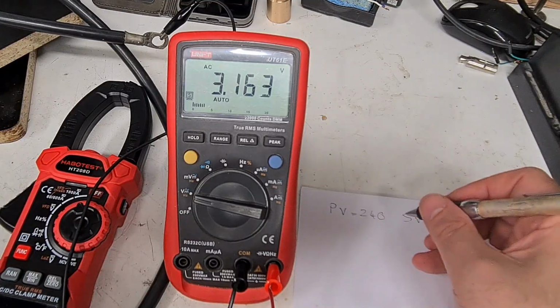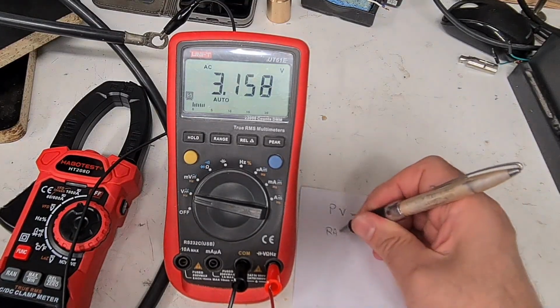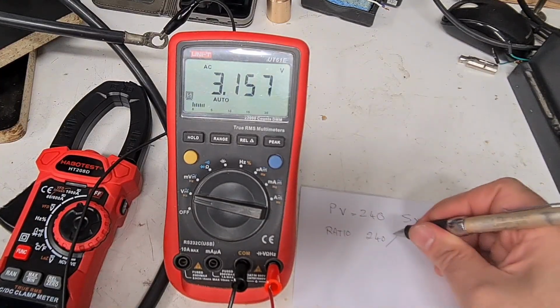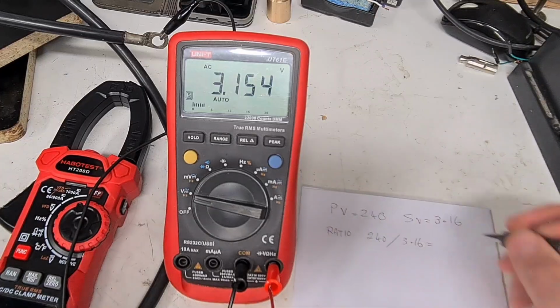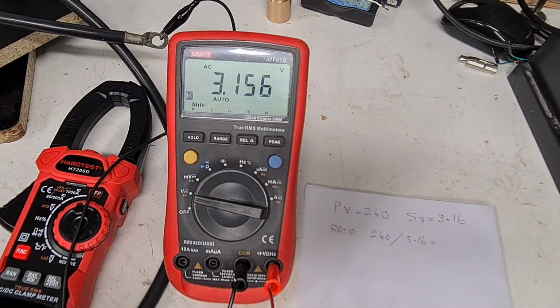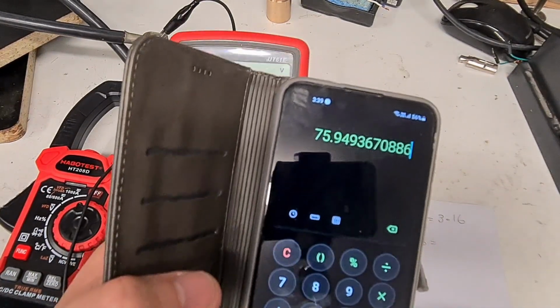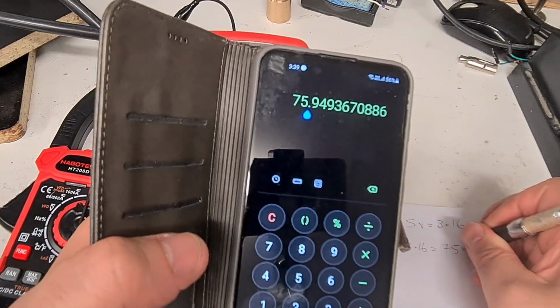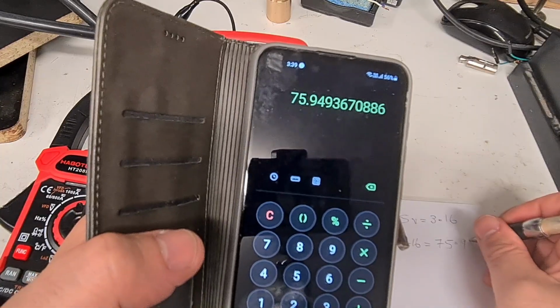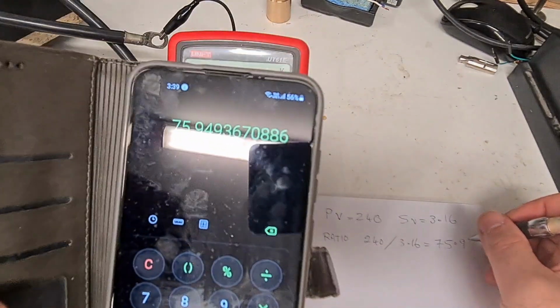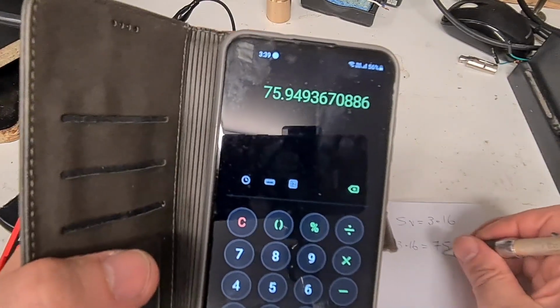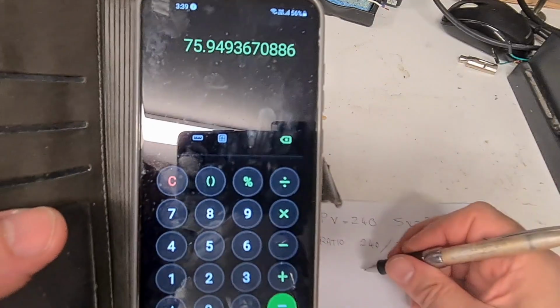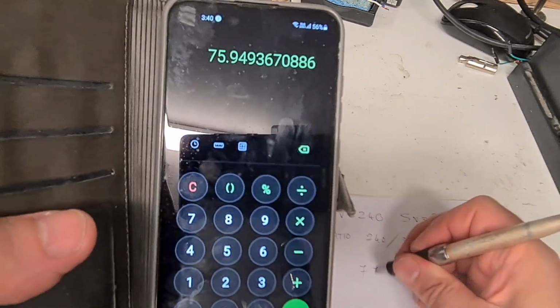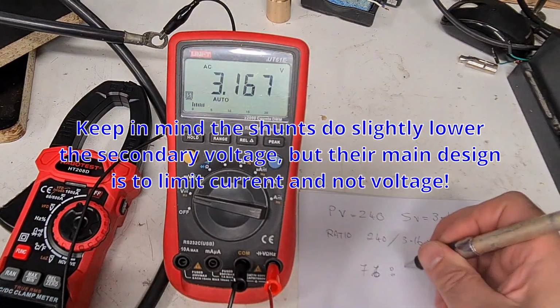Now if we divide, to get the ratio, 240 divided by 3.16 equals... let me get the calculator. 240 divided by 3.16 is 75.9. We can say it's 76, for short. So the ratio is 76 to 1.